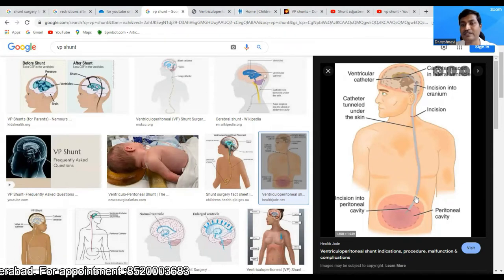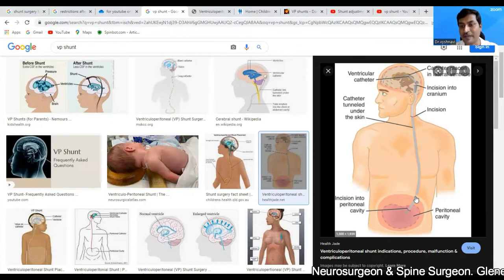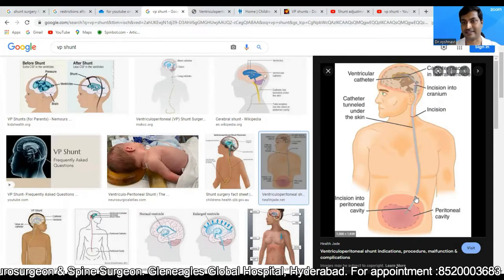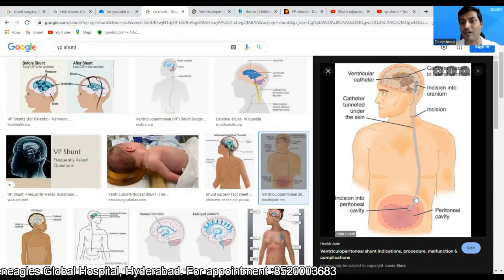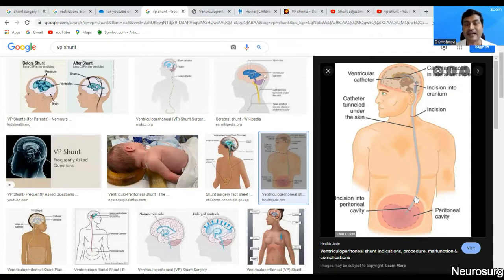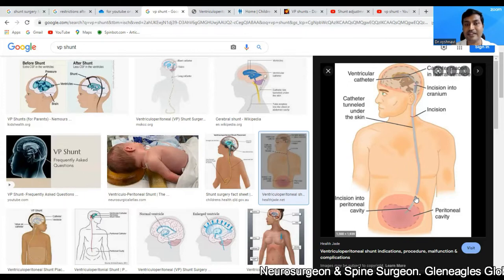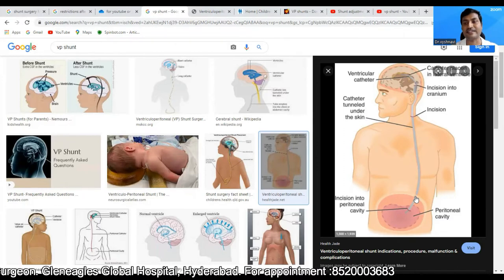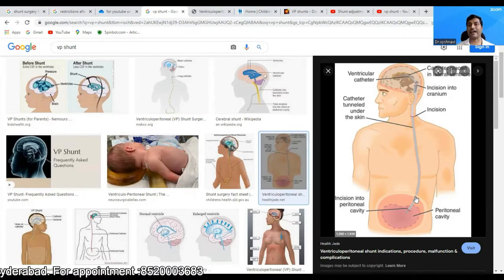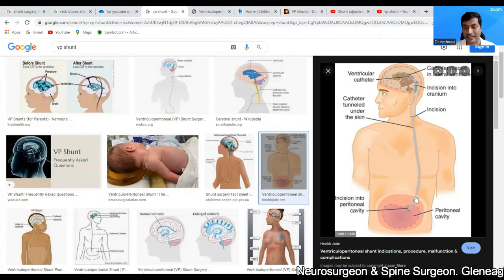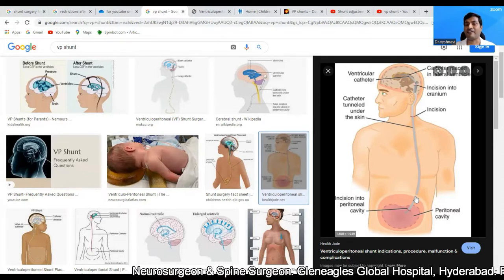The shunt systems are designed in such a way that they let the fluid from the brain go into the peritoneal cavity only when the fluid is in excess — the brain should have some optimum amount of fluid present within itself. Sometimes what happens is the shunt over-drains: even when the CSF within the brain is not excessive, the fluid tends to drain into the peritoneal cavity. This is known as over-drainage.